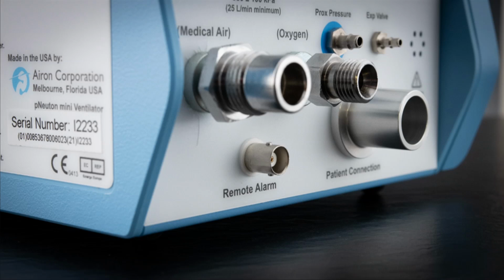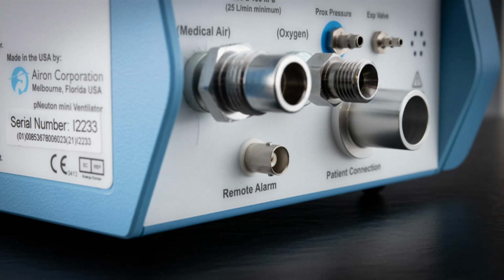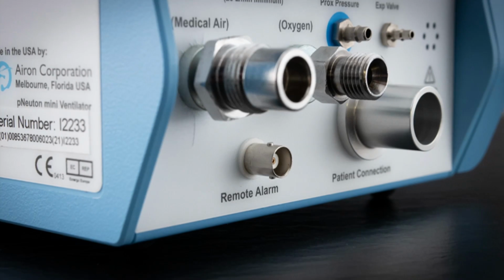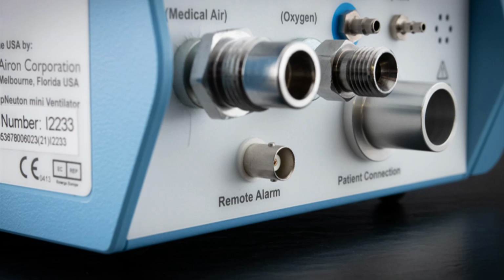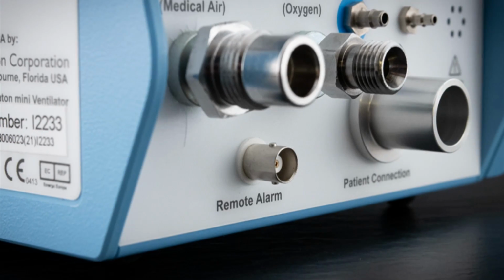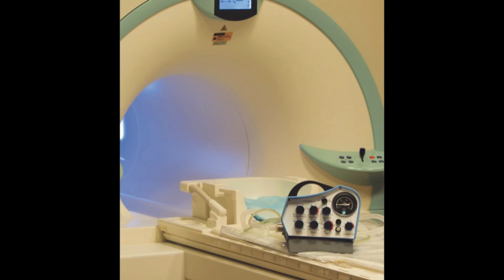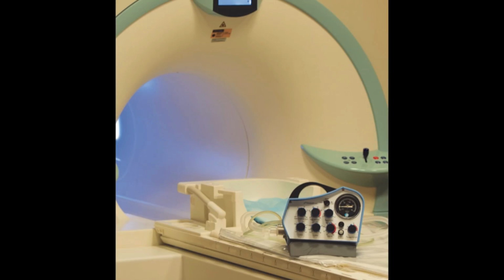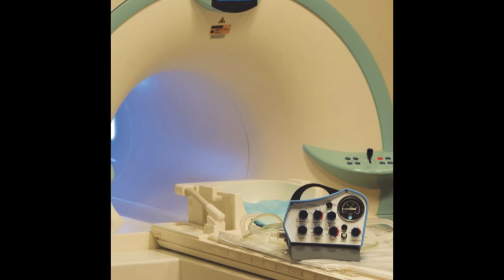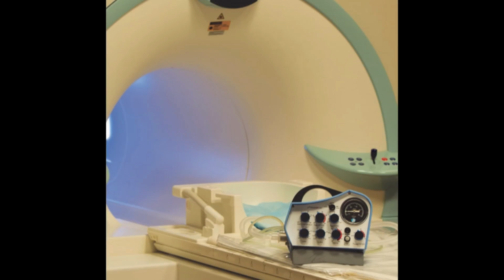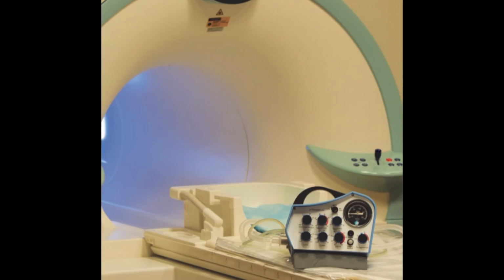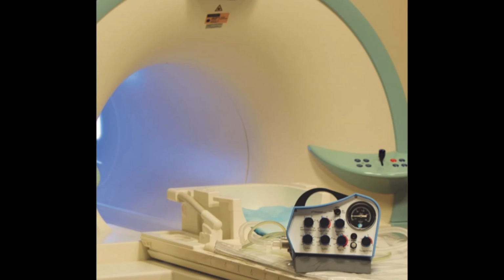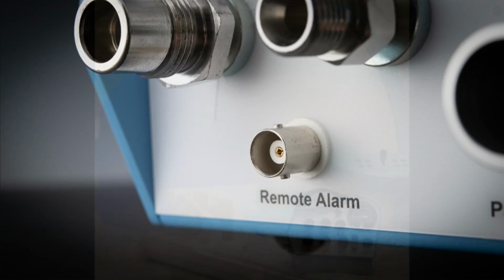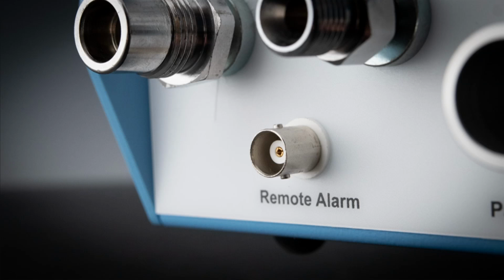Remote alarm output. The next feature to note is the BNC fitting for an optional remote control alarm. This remote alarm fitting will only work with Airon-supplied remote alarm cables. The remote alarm is ideal for use with an MRI transport because it allows the pNeuton Mini to be next to the MRI magnet and an alarm box to be placed in or near the control room, making the alarm audible even while the MRI is running and your patient may not be visible from within the magnet. This provides added safety for your patient and peace of mind for you, the healthcare provider.